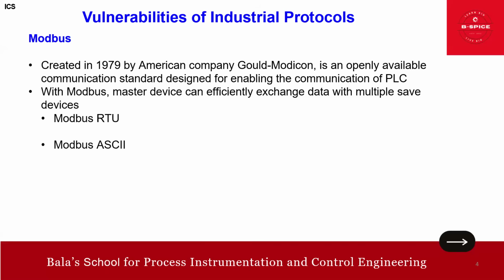Okay. So that's about ASCII and a few more points to add. Modbus ASCII devices can often communicate with Modbus RTU devices with proper configuration and protocol translation. So that possibility is also there. Okay. Another advantage: the format of Modbus ASCII frames makes it human readable, as I mentioned, right? Which can be advantageous for troubleshooting and debugging purposes. So that is another point.